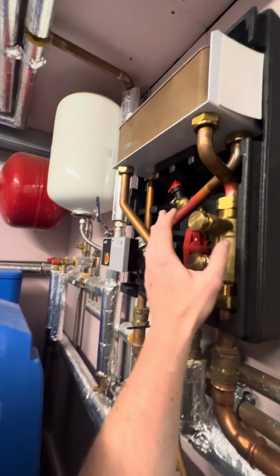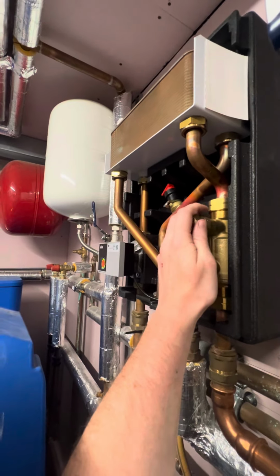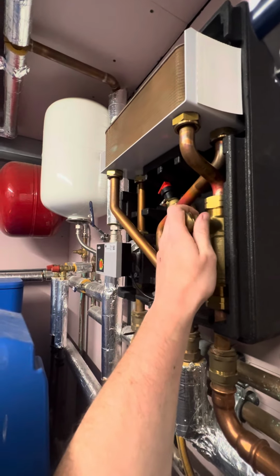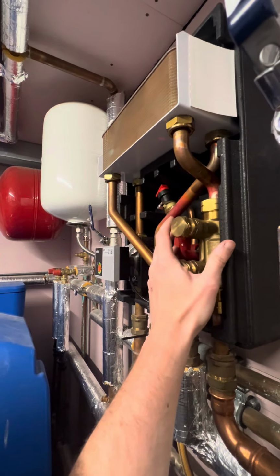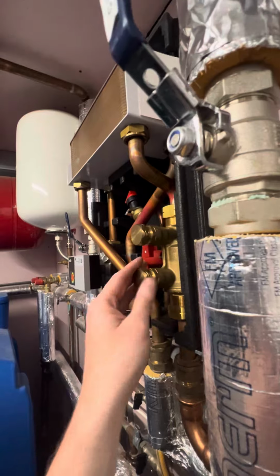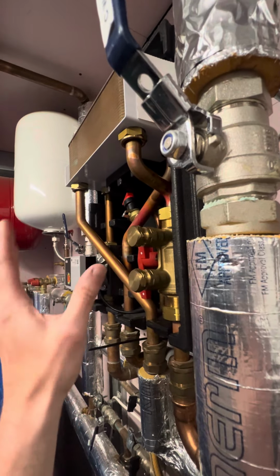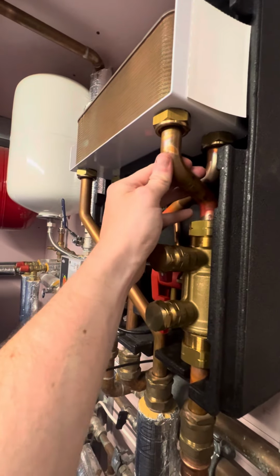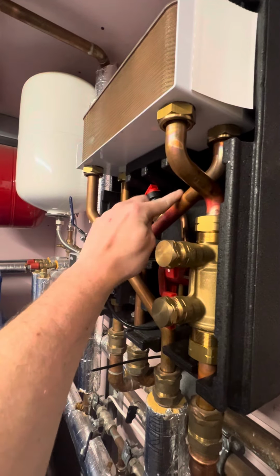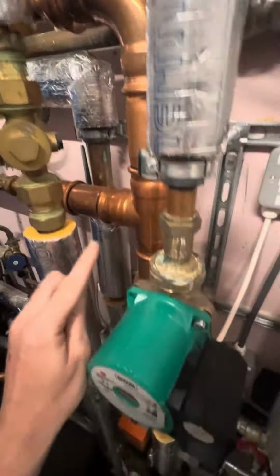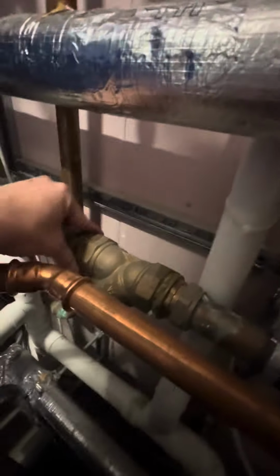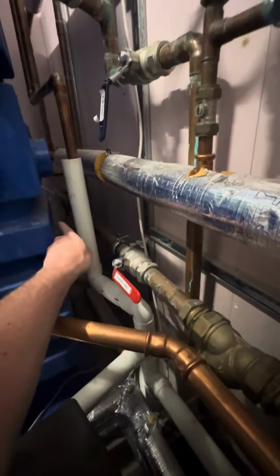Now, we don't install this plate heat exchanger system because this is here so the installers can fill the primary circuit only with glycol, and we prefer to have antifreeze valves rather than glycol because glycol reduces efficiency, it's expensive, and we think it's far better just to simplify it and have the antifreeze valves outside. So because we've got this plate heat exchanger here, it's physical separation, we need a flow back there. From the return, we come down here, and the heating and hot water returns, they tee in, they link up here, and they go back to the heat pump through a filter, primary return filter here, back there, and just before it goes outside, it splits off to the other heat pump.